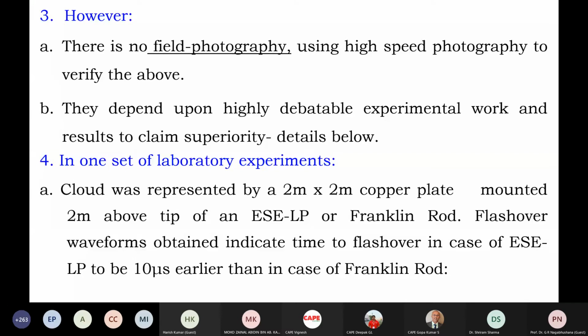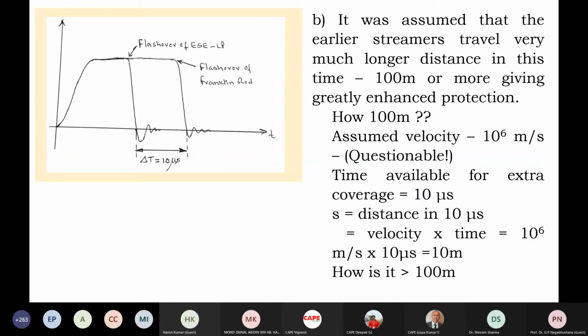In one set of the laboratory experiments, which have been claimed to show the superiority of the ESE system, a cloud was represented by a 2 meter by 2 meter copper plate mounted 2 meters above the tip of an ESE LP or, afterwards, a Franklin rod. The flashover waveforms obtained indicate the time to flashover in the case of ESE LP to be 10 microseconds earlier than in the case of the Franklin rod. Gopakumar also pointed out that. I have shown the possible figures here. The time to flashover is 10 microseconds earlier.